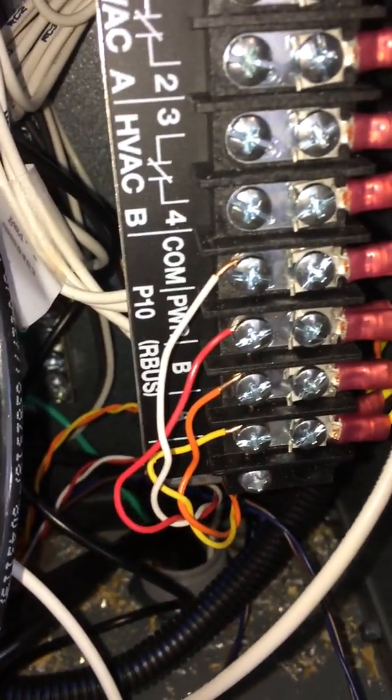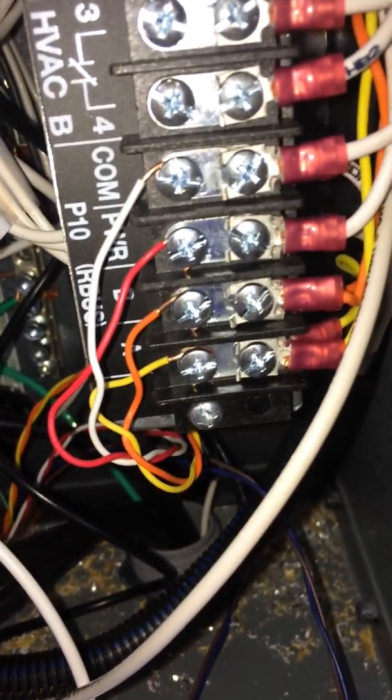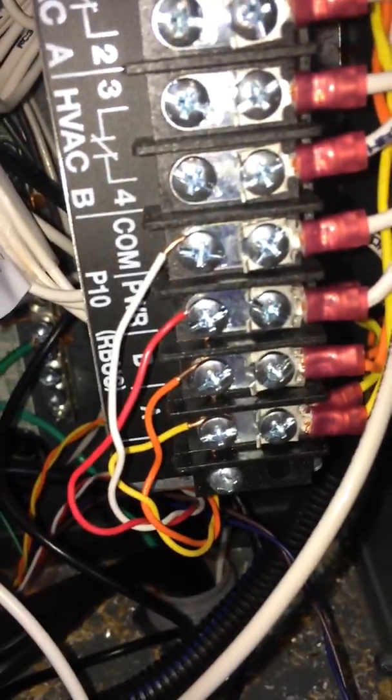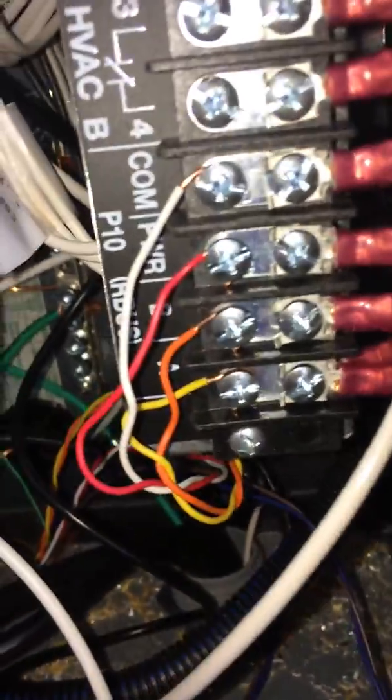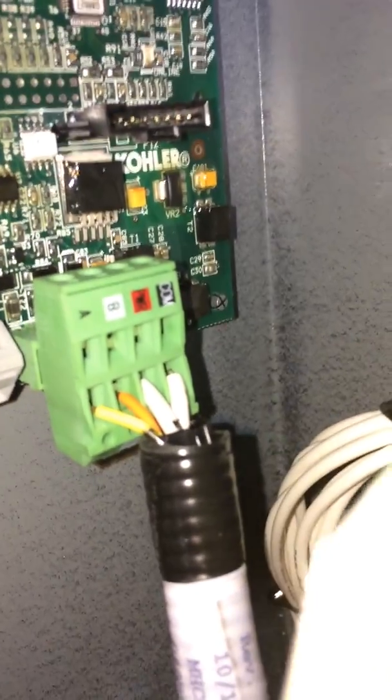The low voltage wiring from the generator has four wires: common, power, A, and B. A and B are the communication wires; common and power are just low voltage. That runs in a separate half-inch conduit with 18 to 20 gauge wire going into the generator. Inside the generator you'll see common, power, A, and B. That's all the control wiring from here to the generator. This whole load module plugs into the board over here. If you weren't using a load control module, A, B, power, and common would go directly into those spots.